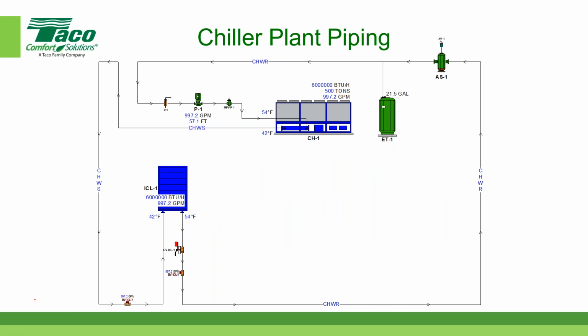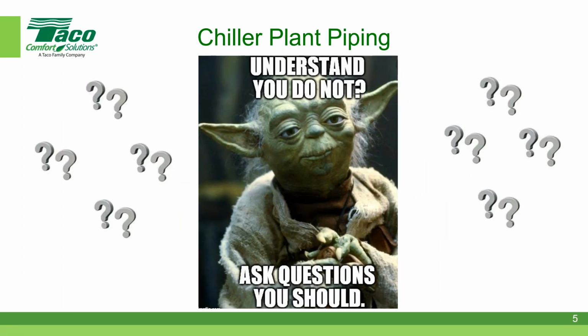Yeah, we have a couple good questions. And the first one's pretty straightforward. Alex is asking, would you recommend using glycol or an electric heating coil to prevent freezing in open cell cooling towers? Well, most open cell cooling towers use a variety of techniques. The most popular is to use a basin heater in the cooling tower so that if you're running the cooling tower in the wintertime, especially if you're doing water-side economizer, sometimes referred to as free cooling, you can keep the basin of the tower from freezing using electric resistance heat inside the basin of the cooling tower.